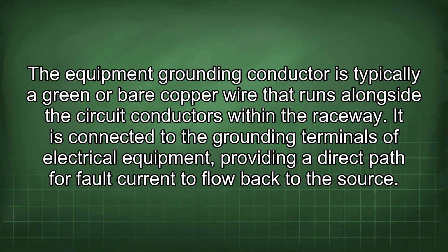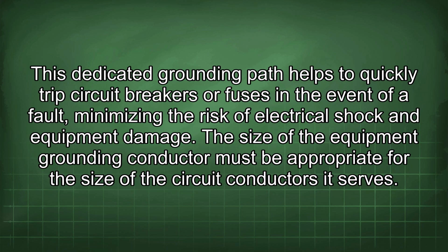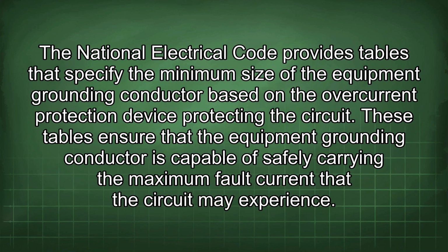The equipment grounding conductor is typically a green or bare copper wire that runs alongside the circuit conductors within the raceway. It is connected to the grounding terminals of electrical equipment, providing a direct path for fault current to flow back to the source. This dedicated grounding path helps to quickly trip circuit breakers or fuses in the event of a fault, minimizing the risk of electrical shock and equipment damage. The size of the equipment grounding conductor must be appropriate for the size of the circuit conductors it serves. The National Electrical Code provides tables that specify the minimum size of the equipment grounding conductor based on the overcurrent protection device protecting the circuit.